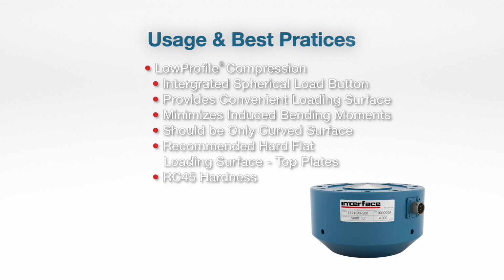All right, so another variation of our 1200 series low profile series would be the low profile compression only version of these load cells. You'll notice they have an integrated spherical load button. It's a very convenient loading surface. Also it gets a little smaller dimensionally. You'll notice we have counterbore base mounting holes on this particular load cell that's pictured. That also helps to minimize any induced bending moments. That spherical load button should be the only curved surface in the load string.